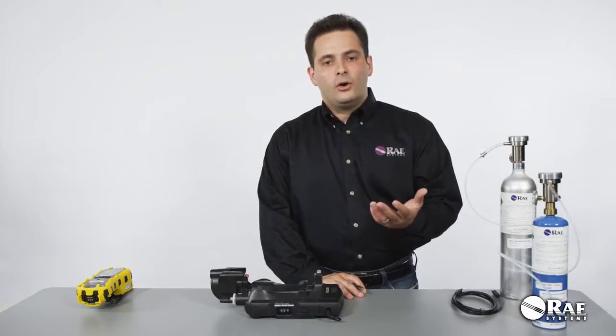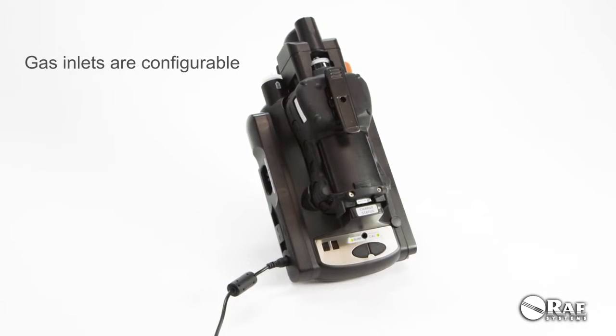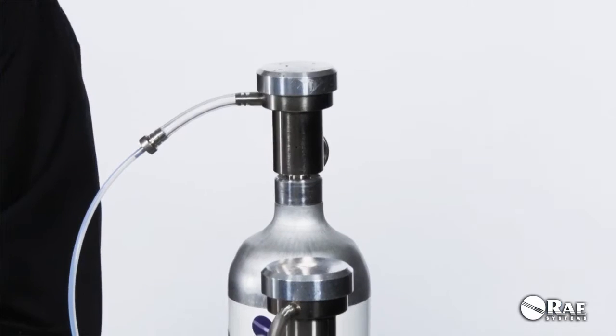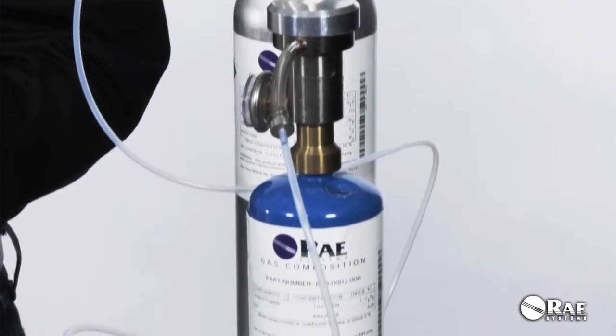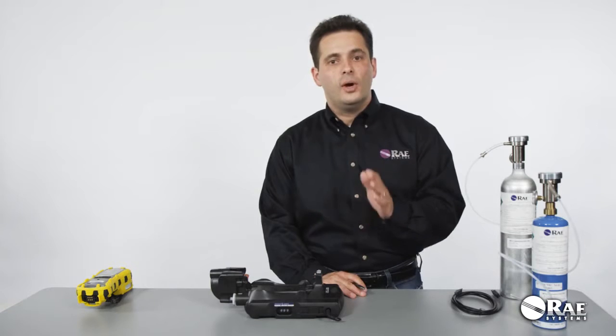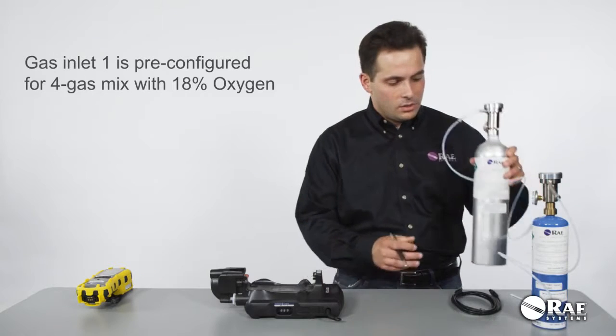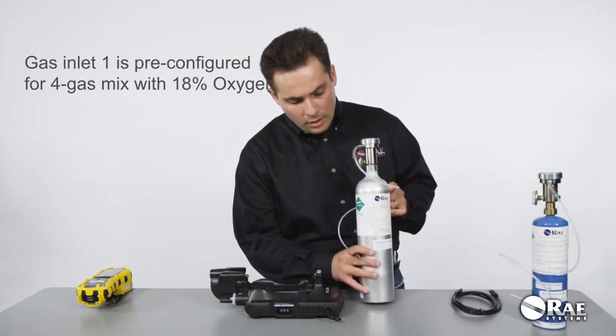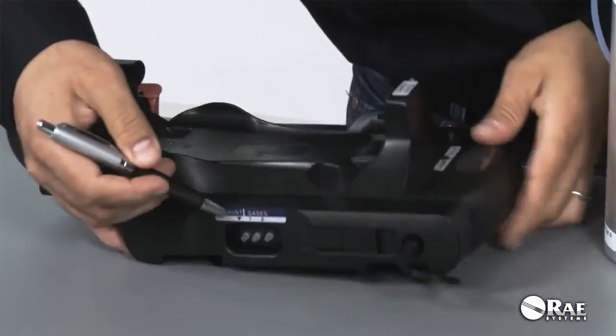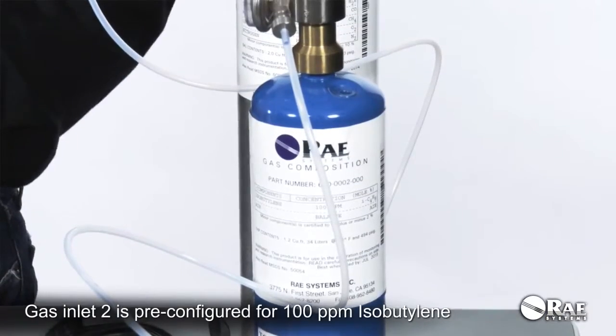The beauty of the AutoRAE 2 is that the inlets are configurable, and you can set them up to match the configuration of your MultiRAE. The default configuration supports the basic MultiRAE setup, which includes the PID, CO, H2S, O2, and LEL sensors. Gas Inlet 1 is configured for a four-gas mix used to calibrate CO, H2S, O2, and LEL. The second inlet is configured for isobutylene, used to calibrate the PID sensor.